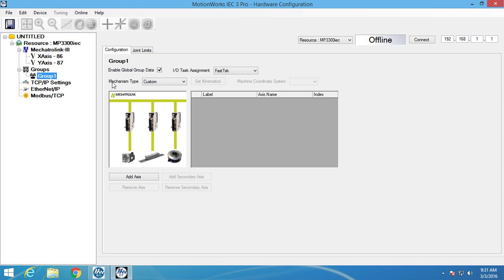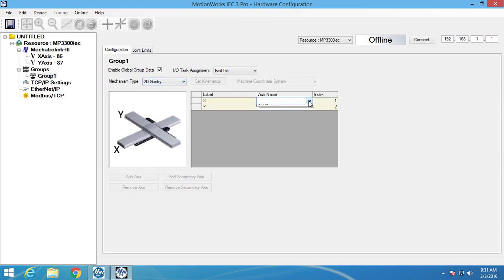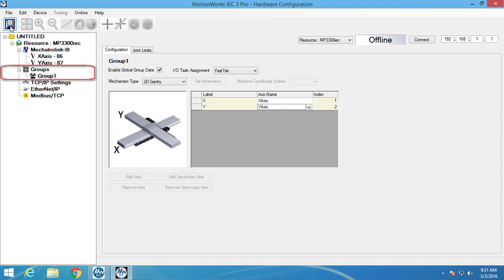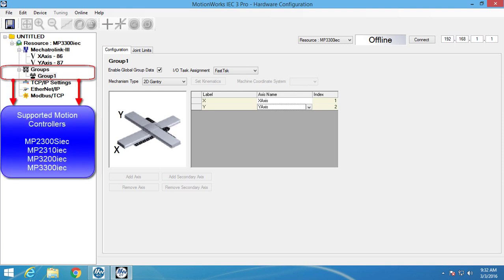In these groups, you can select what mechanism you will be working with, and then you can add the axes into the required areas of the system. Once this configuration is saved, your machine can then be programmed. The groups tree selection is not supported in the MP2600iec controller because it's a single-axis controller, but it is supported in all the other MP2000iec and MP3000iec series controllers.